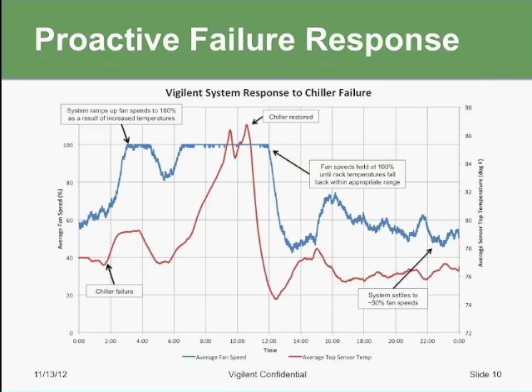And then on the right y-axis is the average temperatures, indicated by the red line. So what happened at about 2 o'clock in the morning is the chillers had failed, and none of the facility staff were there at the time. And you can see as the temperatures start to go up, the fan speeds immediately respond to that and start ramping their fan speeds up to provide as much cooling as possible using the chilled water loop.